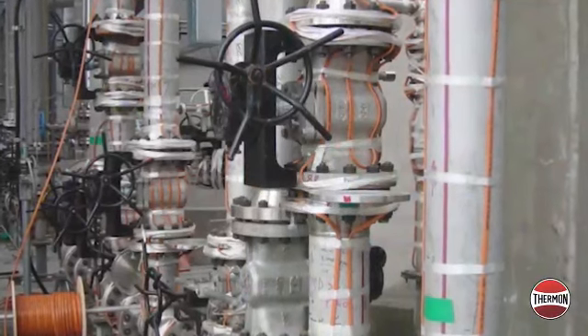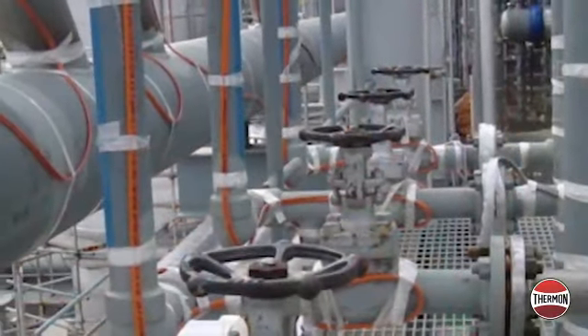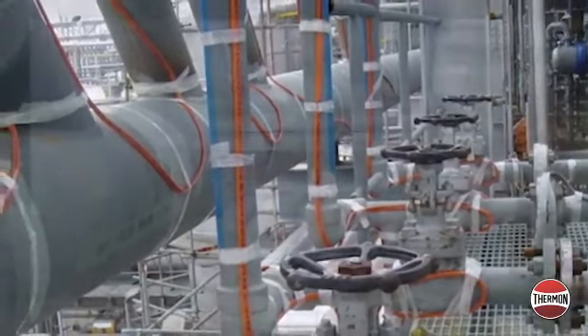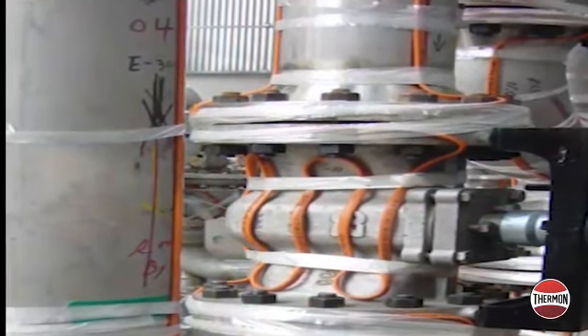Thermal equilibrium is the balance between the heat that's being lost through the thermal insulation and the heat that's being returned to the system via a heat source. Typically in our application, this heat source is a heat tracer. Many refineries and chemical plants still select low-pressure steam tracing for their winterization. However, most new freeze protection system installations rely on electrical heat tracing.